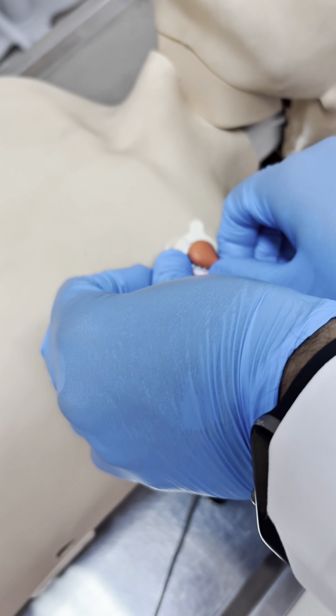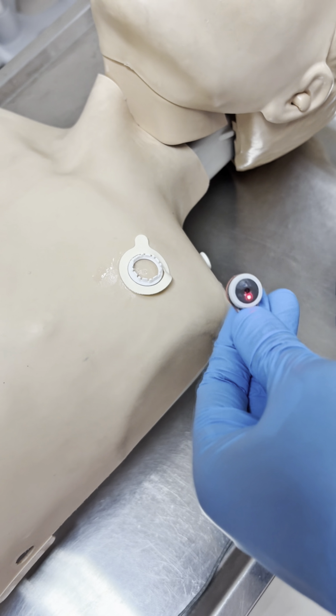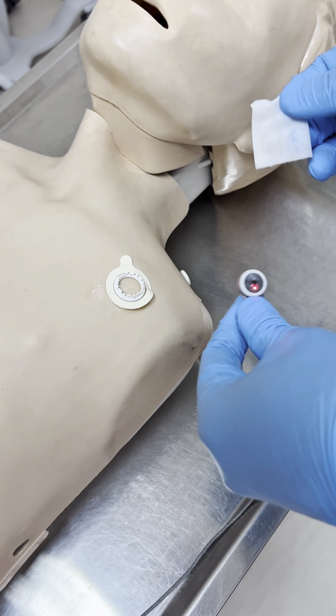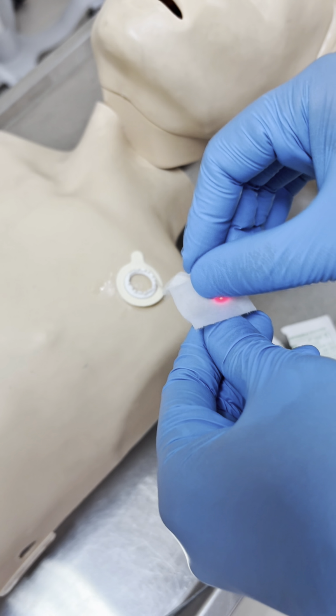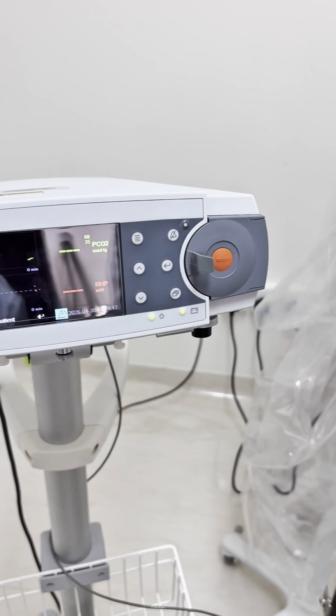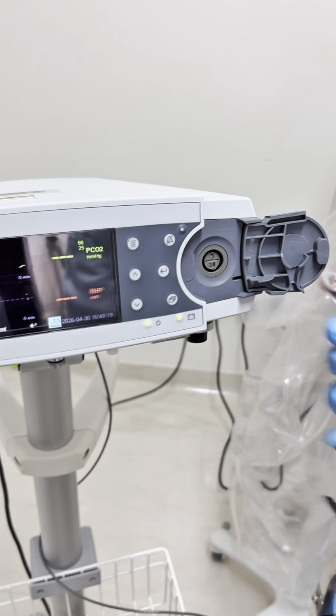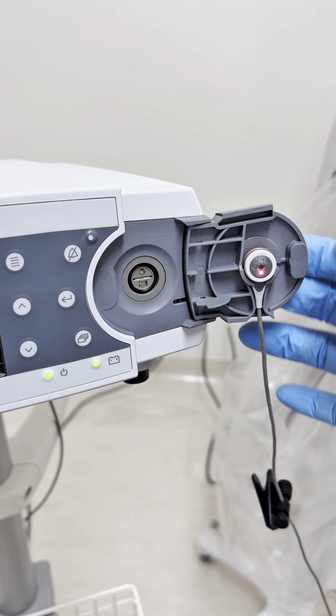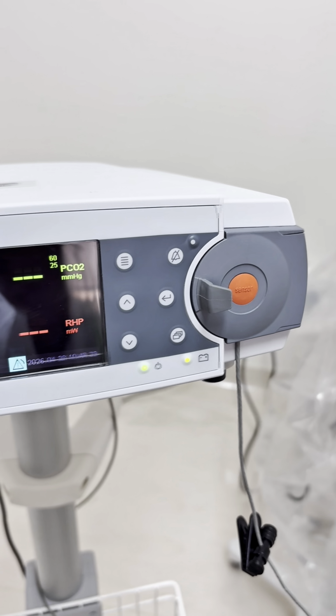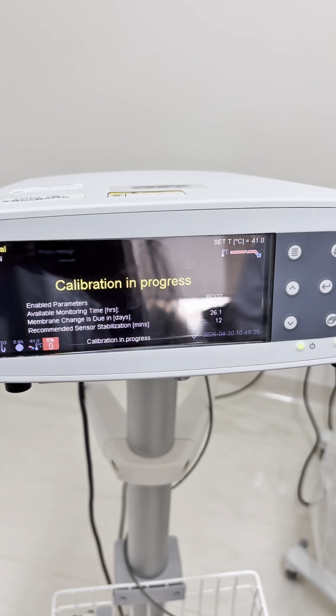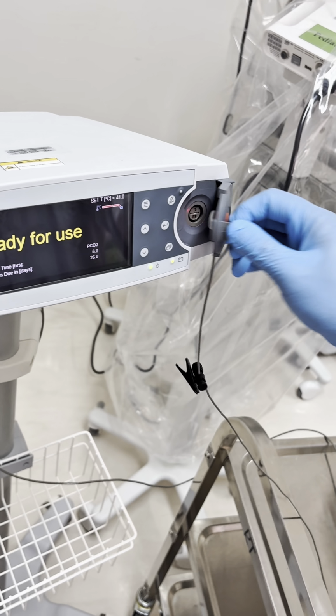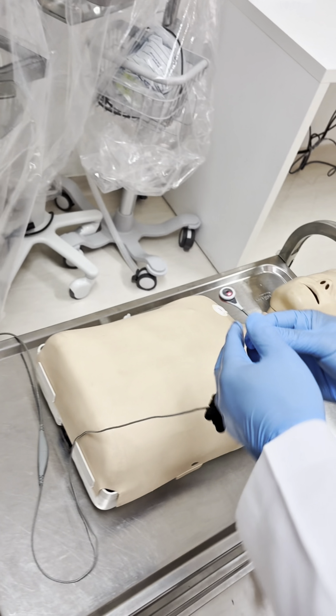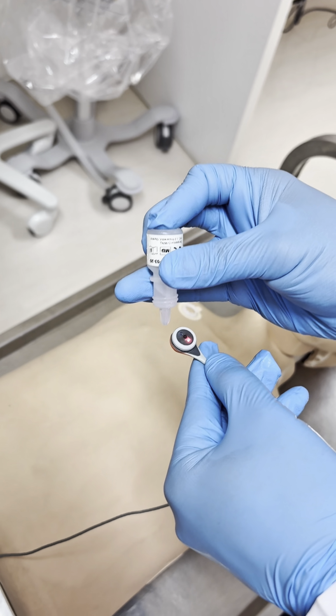To alternate the site, remove the sensor from the attachment ring. You must gently wipe the sensor surface with an alcohol swab to make sure it is clear from the gel. Place the sensor correctly back into the docking station and close the door. The device will do a calibration. This process is mandatory between site-to-site alternation. Again, with the same previous site steps, apply the sensor onto the new site.